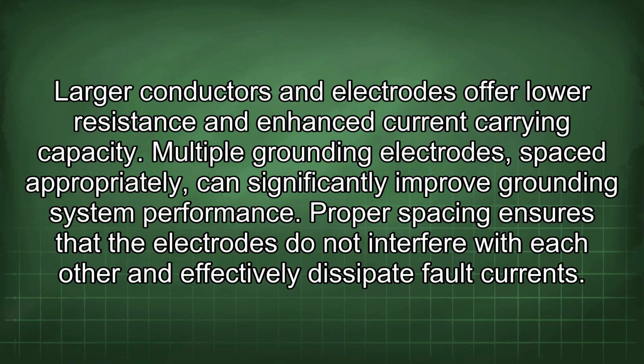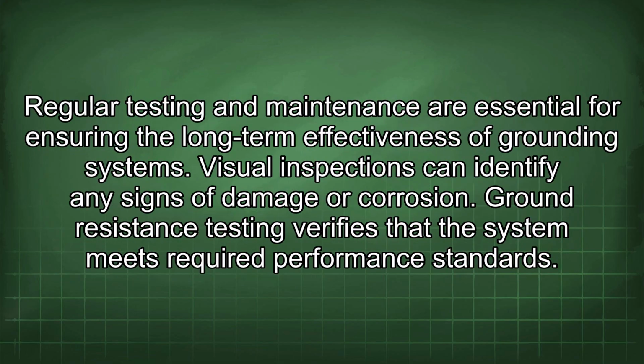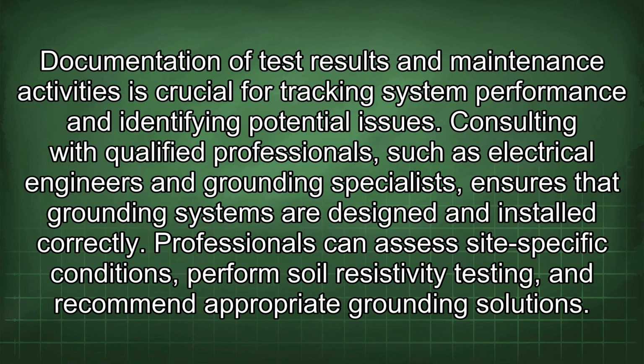Multiple grounding electrodes, spaced appropriately, can significantly improve grounding system performance. Proper spacing ensures that the electrodes do not interfere with each other and effectively dissipate fault currents. Regular testing and maintenance are essential for ensuring the long-term effectiveness of grounding systems. Visual inspections can identify any signs of damage or corrosion. Ground resistance testing verifies that the system meets required performance standards. Documentation of test results and maintenance activities is crucial for tracking system performance and identifying potential issues.